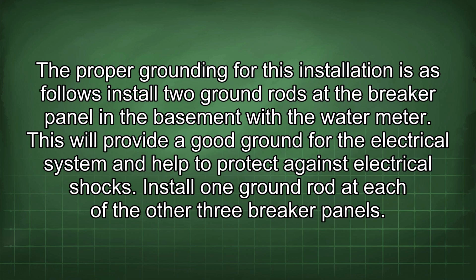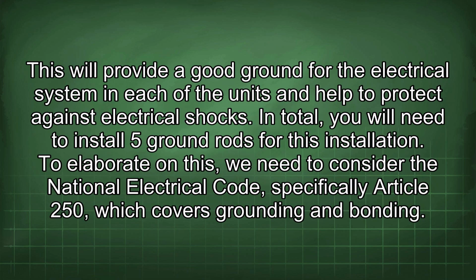Install 1 ground rod at each of the other 3 breaker panels. This will provide a good ground for the electrical system in each of the units and help to protect against electrical shocks. In total, you will need to install 5 ground rods for this installation.